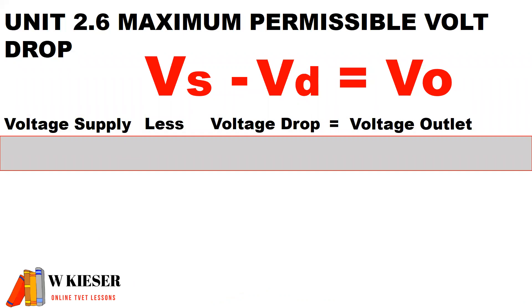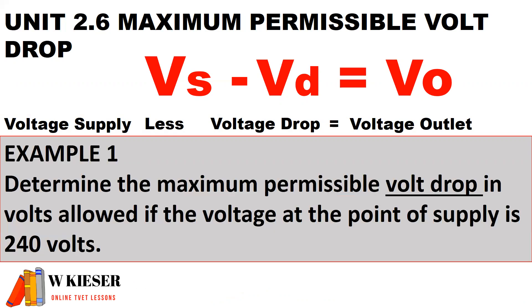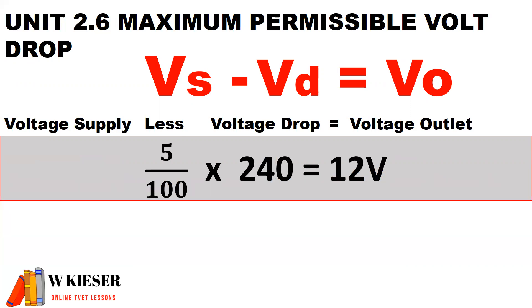Now we're going to get some calculations for this module. The first type of calculation is calculating the maximum permissible volt drop. The formula is: voltage supply minus the volt drop equals the outlet voltage. It is important to note that the volt drop cannot be more than 5% of the supply. In this example, determine the maximum permissible volt drop in volts if the voltage at the point of supply is 240 volts. We calculate 5/100 × 240 volts. Therefore, the volt drop cannot be greater than 12 volts.